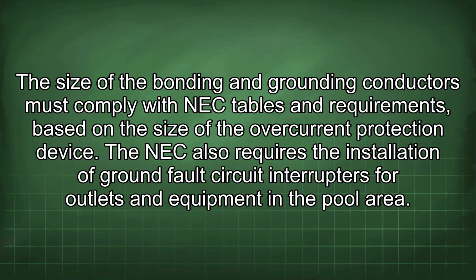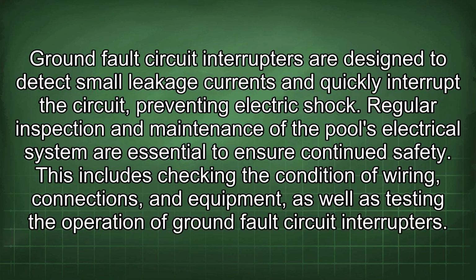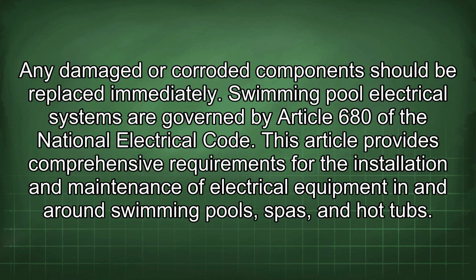The size of the bonding and grounding conductors must comply with NEC tables and requirements based on the size of the overcurrent protection device. The NEC also requires the installation of ground fault circuit interrupters for outlets and equipment in the pool area. Ground fault circuit interrupters are designed to detect small leakage currents and quickly interrupt the circuit, preventing electric shock. Regular inspection and maintenance of the pool's electrical system are essential to ensure continued safety. This includes checking the condition of wiring, connections, and equipment, as well as testing the operation of ground fault circuit interrupters. Any damaged or corroded component should be replaced immediately.